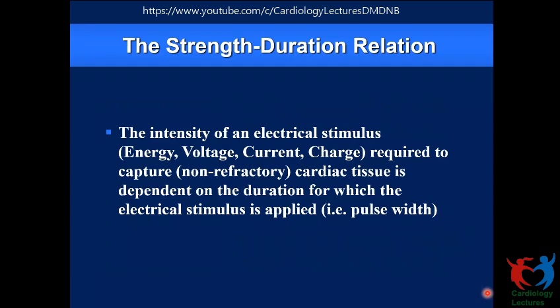As I said, there is a relationship between the output that we are delivering, in terms of voltage or current or charge, and you can also relate it to energy, and the duration for which we are delivering the pulse. That is the strength duration relationship. In a pacemaker, we generally control the voltage, so we can imagine this to be a voltage to duration relationship. It is the intensity, or amplitude, of the voltage that is required to capture non-refractory myocardial tissue, and this depends on the duration. It varies according to that. That's the strength duration relationship.